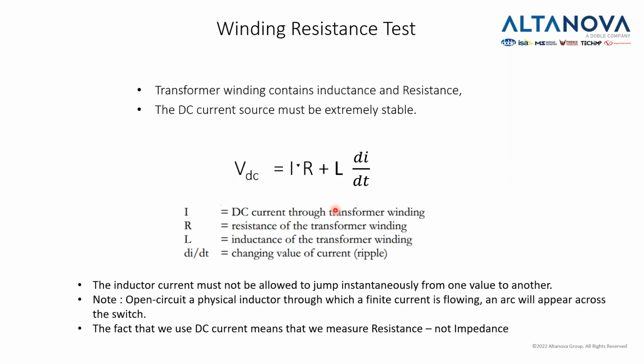An important thing to emphasize in this test is that we are generating DC current. That's why we call it winding resistance, not winding impedance. So DC current is being generated, and we are measuring the voltage drop. Now, since the voltage drop depends on the resistance, this is the current we are generating on the resistance, but we can see that in this equation there is also the inductance. We want this part L di/dt to become zero so that we can measure the resistance. That's why in some cases the measurement of a single phase on a single position of the tap changer can take 2, 3, 4 minutes, depending on how big the transformer is.